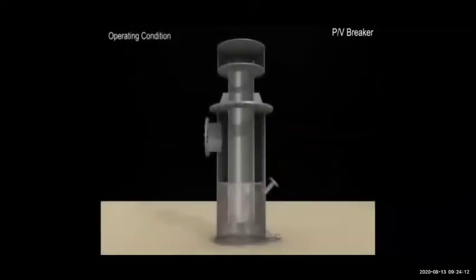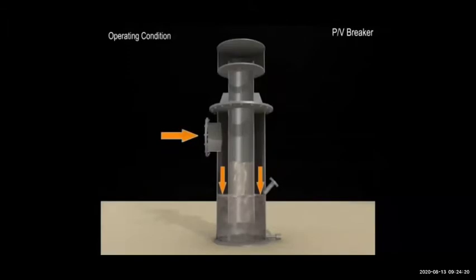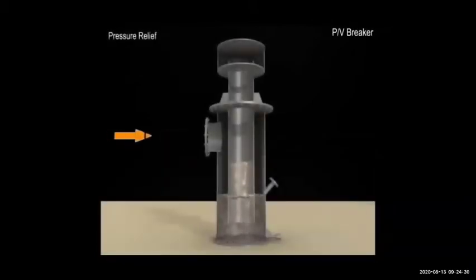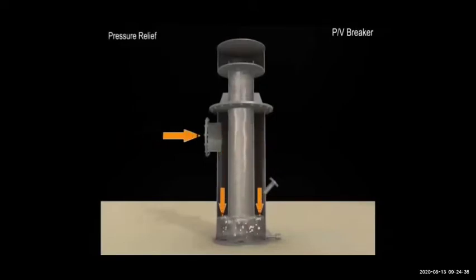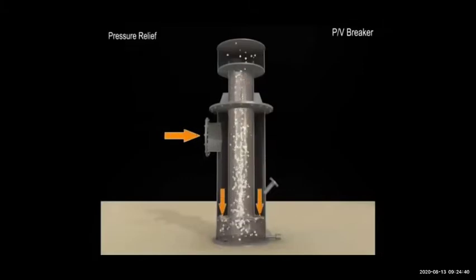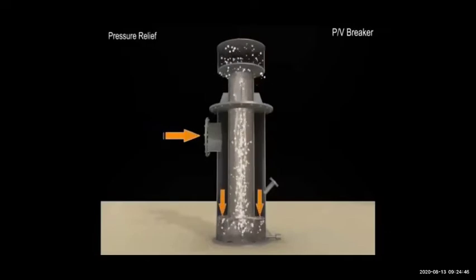Inert gas is coming from the pipeline and pushing the water. Because pressure is normal, it cannot push the water, so the gas keeps passing through to other tanks. But if the pressure is too much, it will push all the water out of the PV breaker and the gas will come out to atmosphere. If water is coming out of the PV breaker, that means pressure is very high. You can also check pressure from CCR sensors.